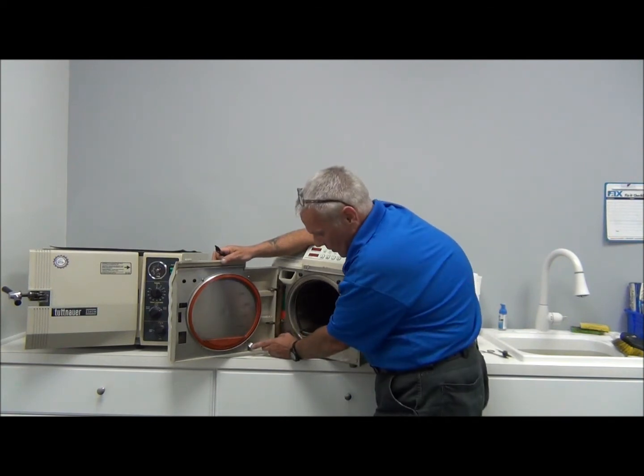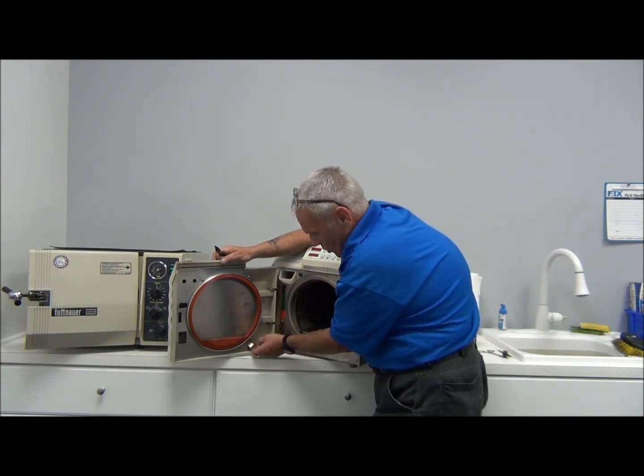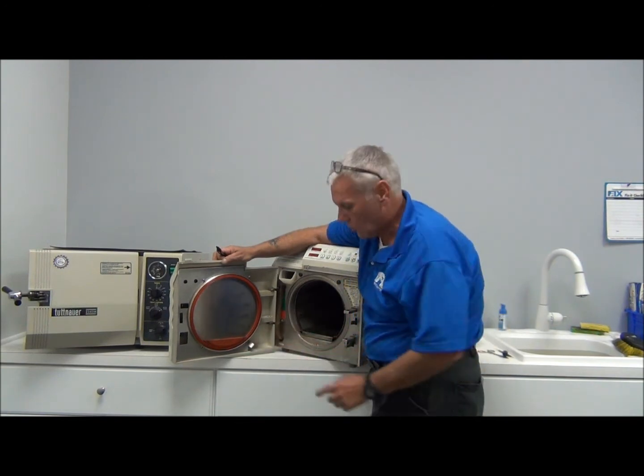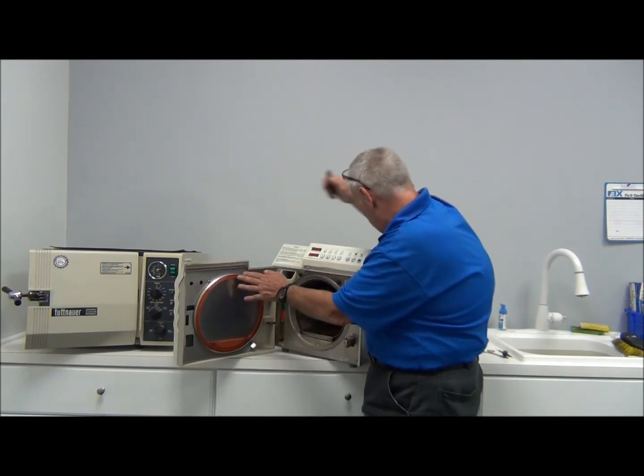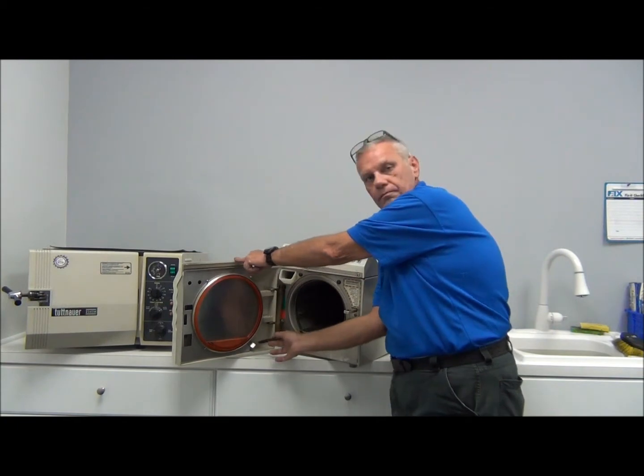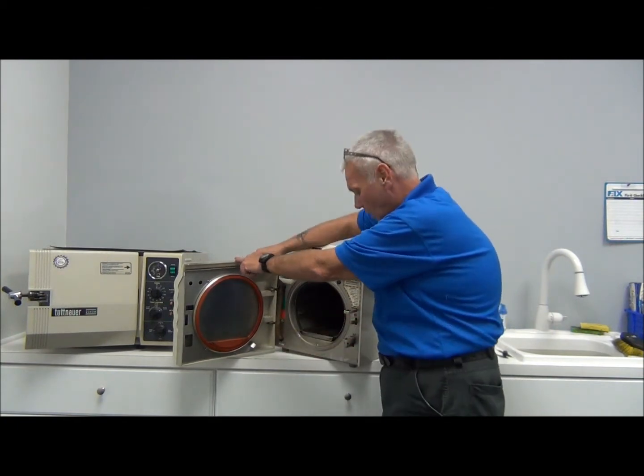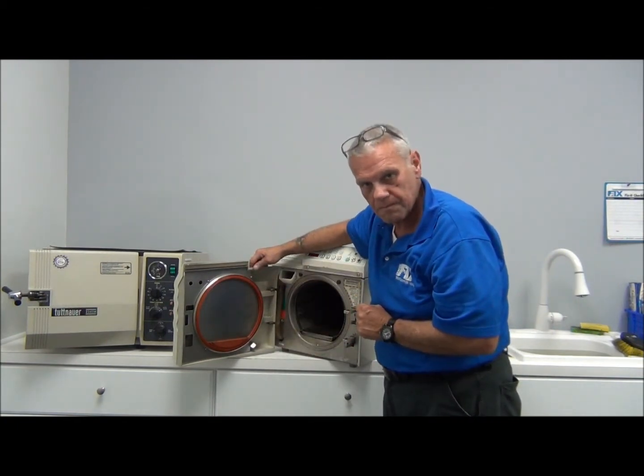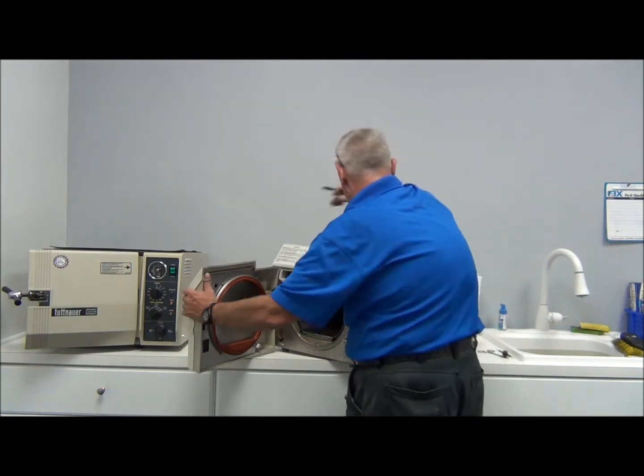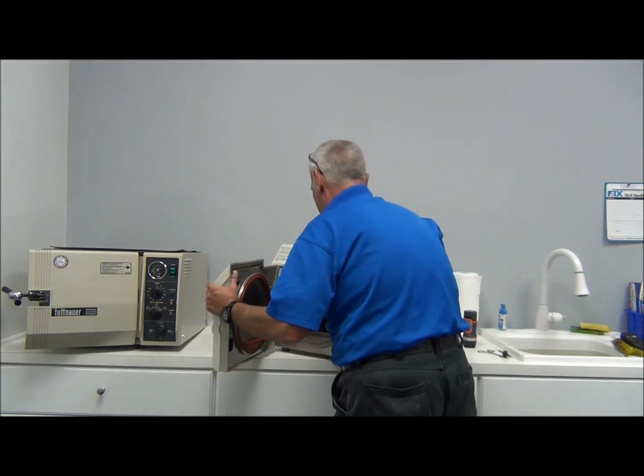Second step is inspect our door springs. We want to make sure we have at least one intact door spring at a 4 o'clock angle, like so. Sterilizer will not function properly without the door springs. Okay, let's set the sterilizer back up.